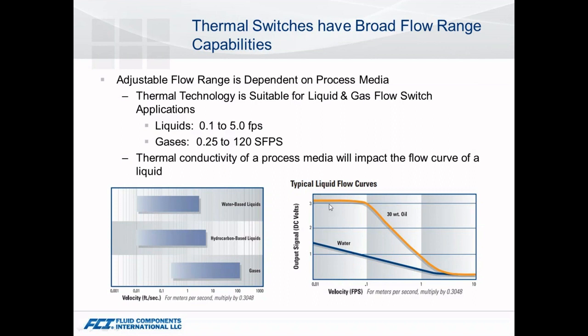To illustrate that difference, if you look at a flow curve for water media versus oil, it varies quite a bit, and a lot of that is due to thermal conductivity. This is key because a lot of times you're dealing with a constant liquid. If you're doing a flow switch application, maybe monitoring the pump of a vessel, sometimes you might be dealing with aqueous solutions. An area to keep in mind is if that percent concentration changes, the thermal conductivity is going to affect that curve. In those cases, you might look more for a flow/no-flow type application rather than trying to hit a very specific value — because if you calibrate for one solution and then change that solution by 5% or 10%, it's going to trip at a slightly different value.